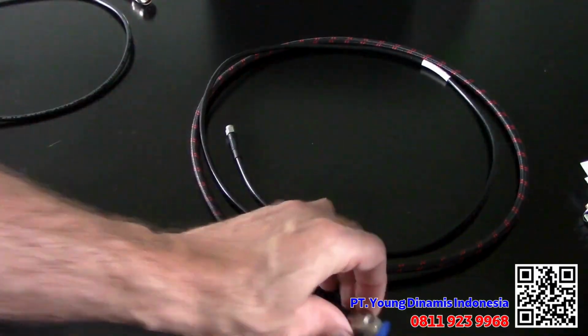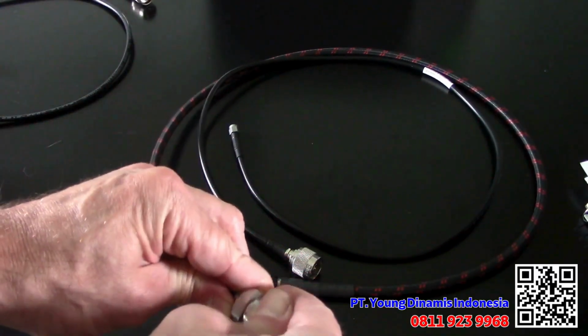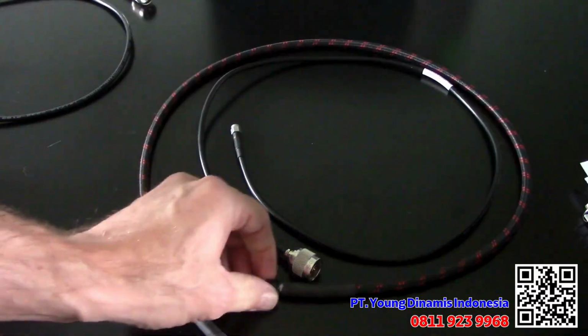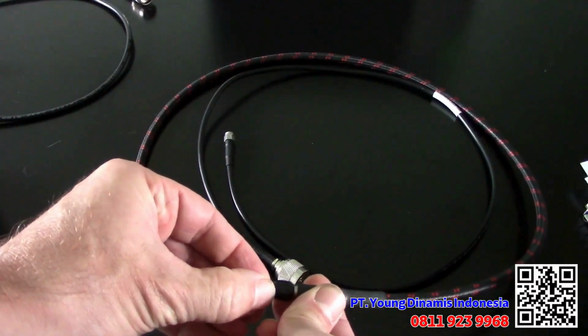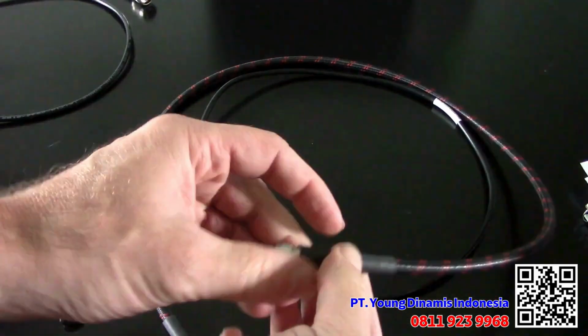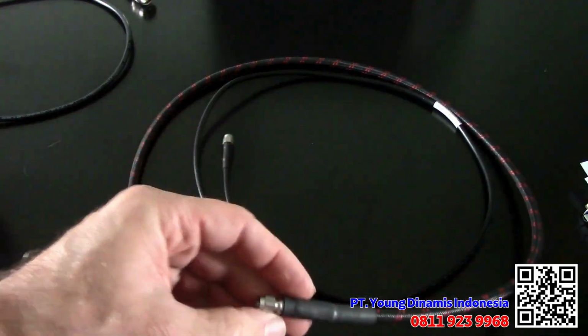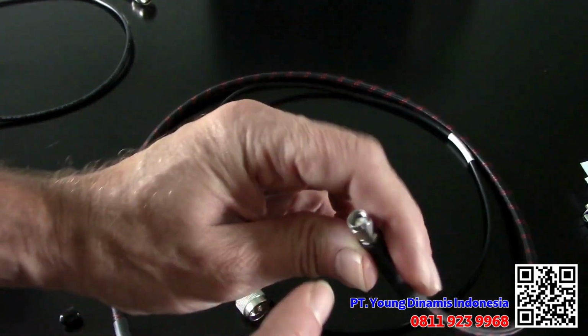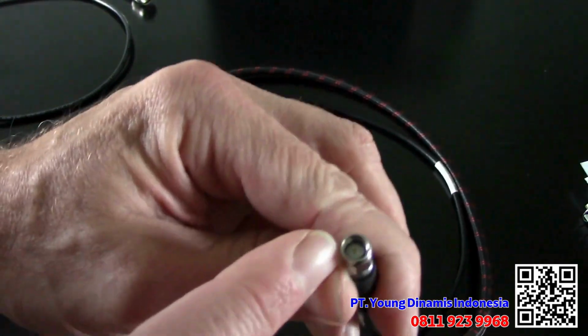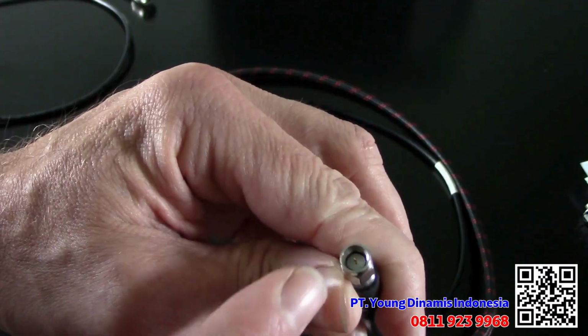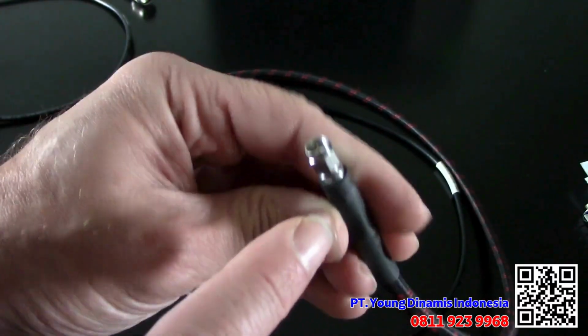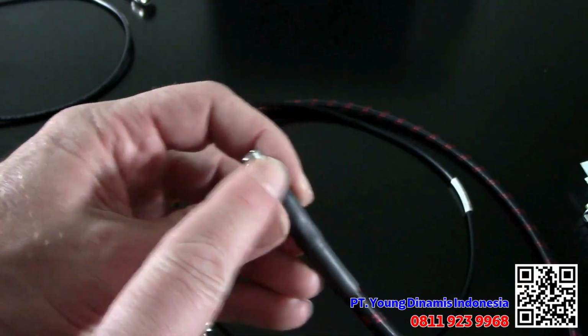And we've got a higher quality cable here, also terminating on an N-type on one end, SMA on the other. Some of the things we're going to want to look at when we're judging the quality: we want to look at the material type. Are the plating materials quality? Are they flaking or are they solid? We want to look at the conductor. Is that center conductor centered on the dielectric?